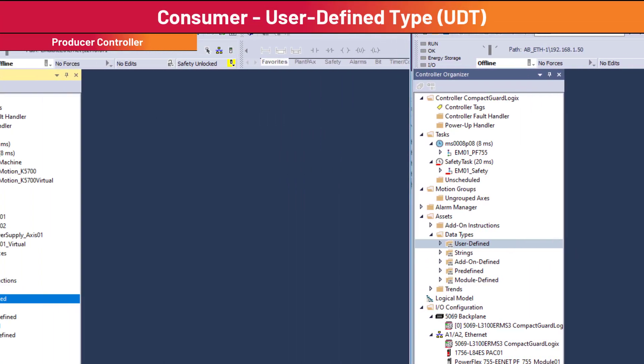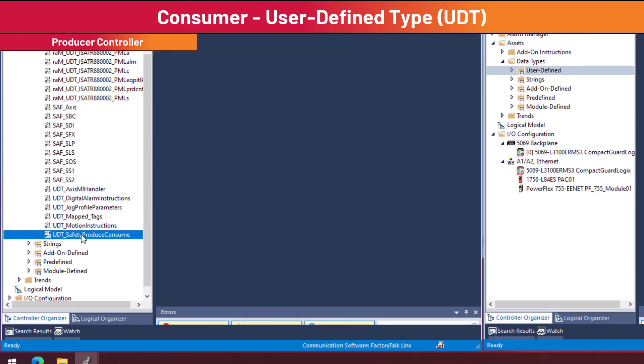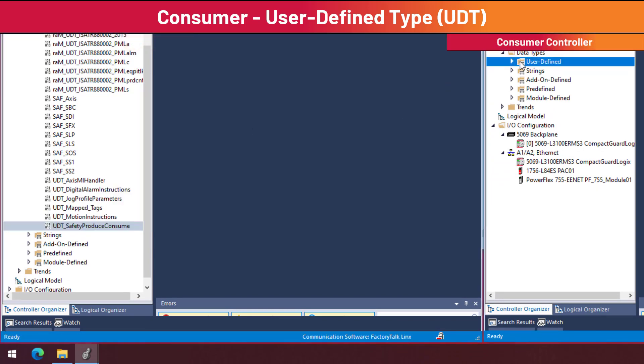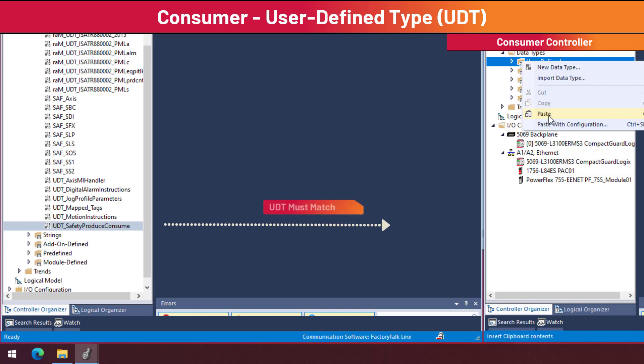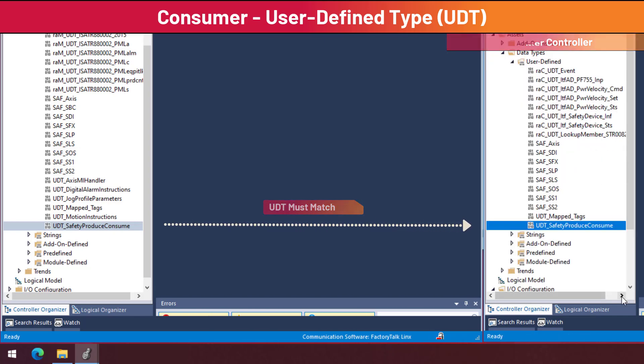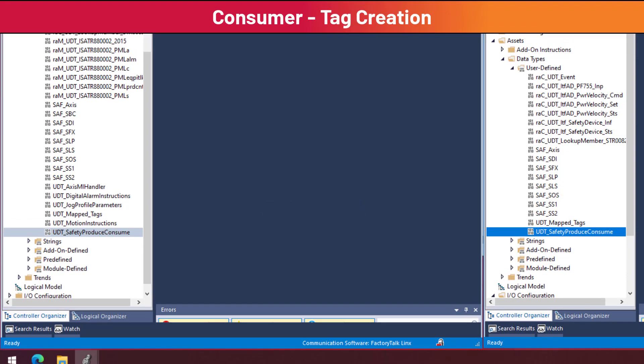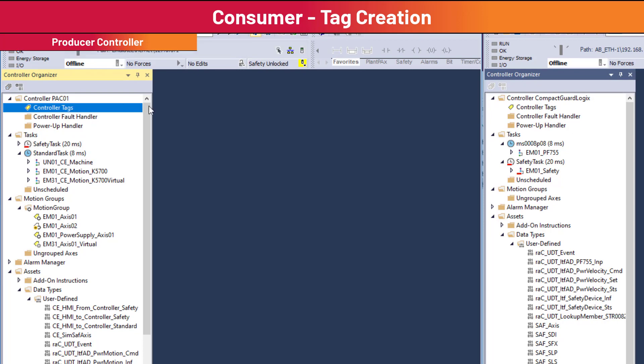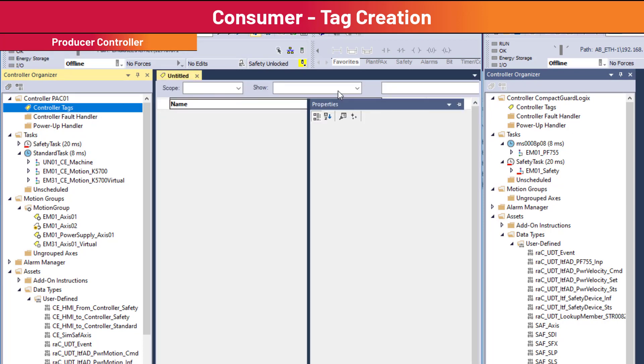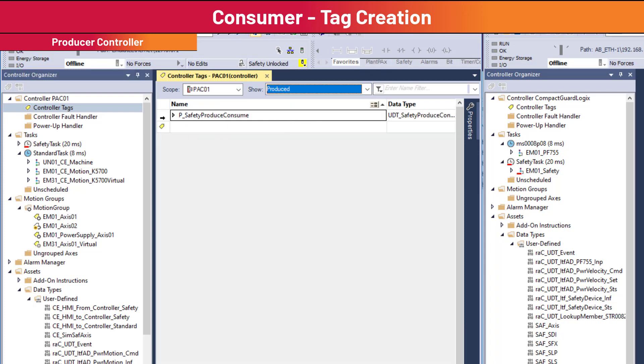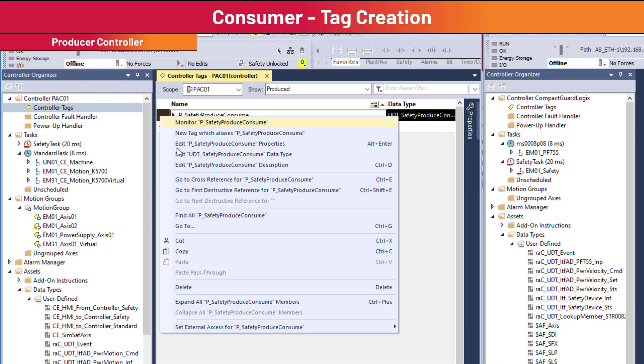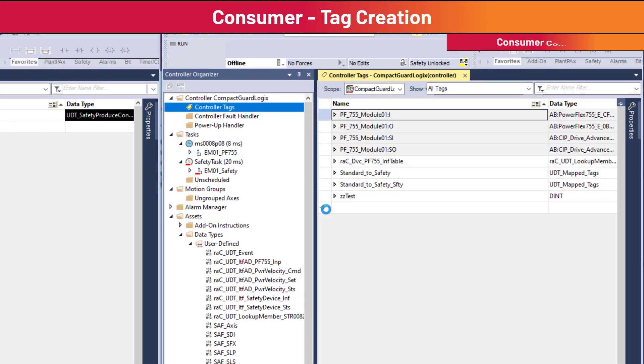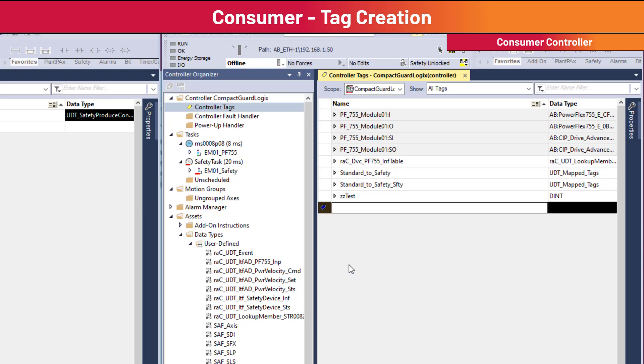Copy the produce/consume user-defined data type from the producer controller. Create a controller scope tag with data type UDT_safety_produce_consume. An easy way is to copy the already created produce tag from the producing controller, then paste that tag into the consumer controller tags.